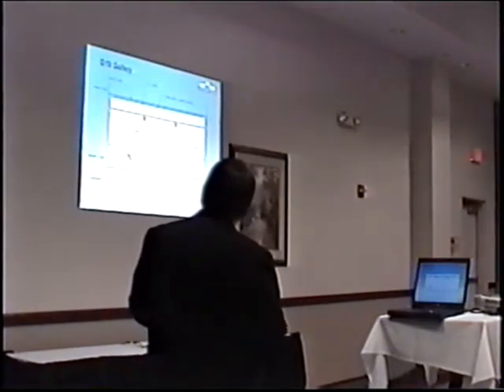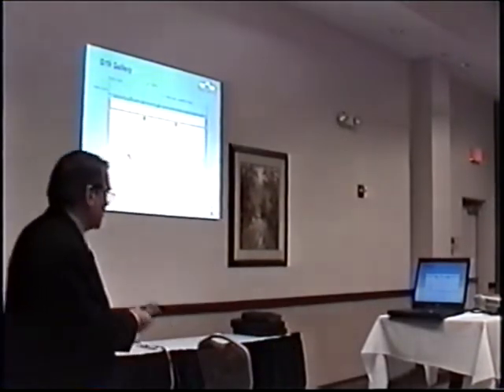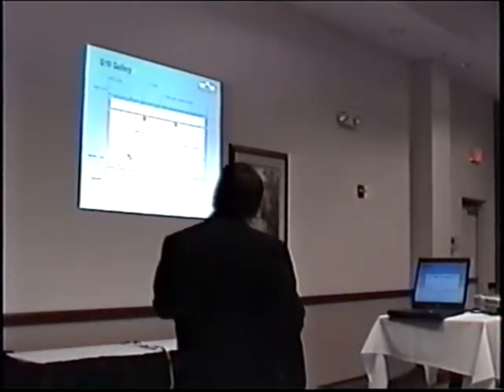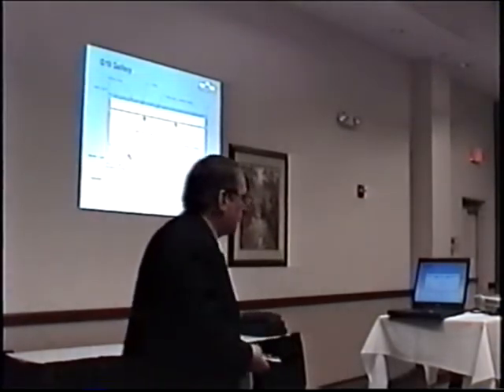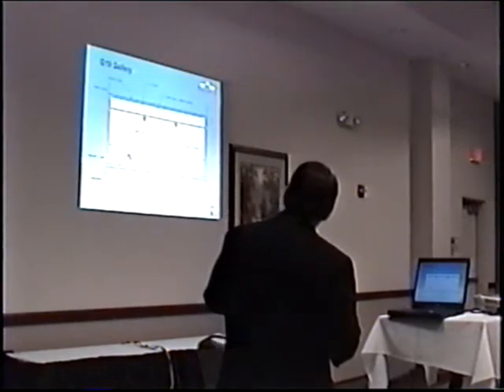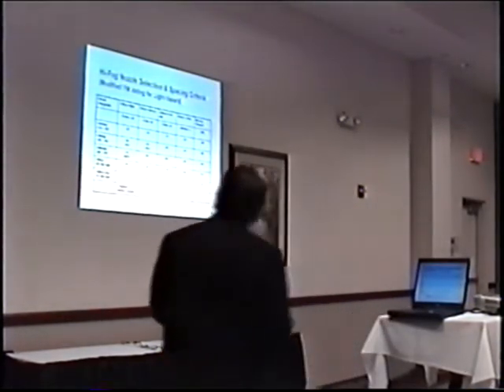A couple things to note here. Ceiling height's 5.4 meters, while the nearest approval for a light hazard water mist nozzle was 5 meters. What the heck, we'll get around that one. We have about a 15 meter by 7.4, basically 50 feet by 25 foot room. 16 foot floor to the ceiling.